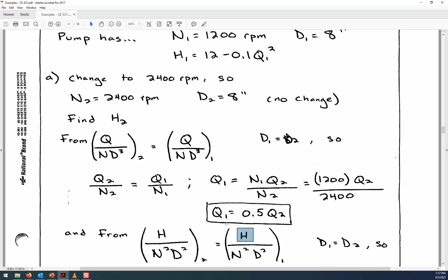It wouldn't have been that kind of linear relationship like it is so far. Okay, but the next step is we need to find out how does the performance curve change? From the second of our two scaling laws that we're using, we get the relationship between the pump head of this new pump, pump 2, compared to the pump head of the first pump. And so we're going to be solving for H2 in terms of H1, because with this first one, we're going to substitute in here, so where it says Q1 from our existing equation, we're going to substitute in 0.5 Q2.